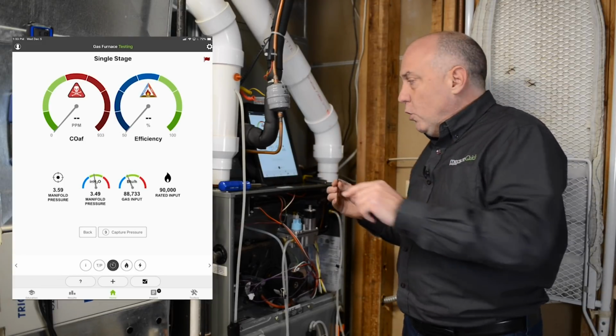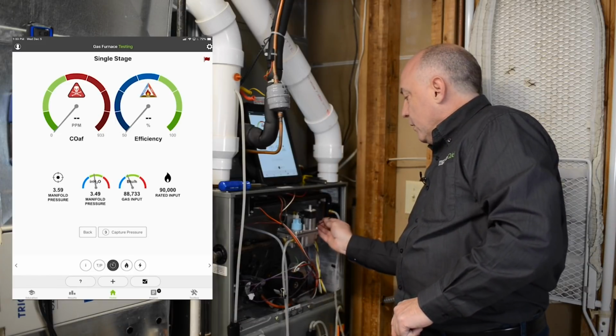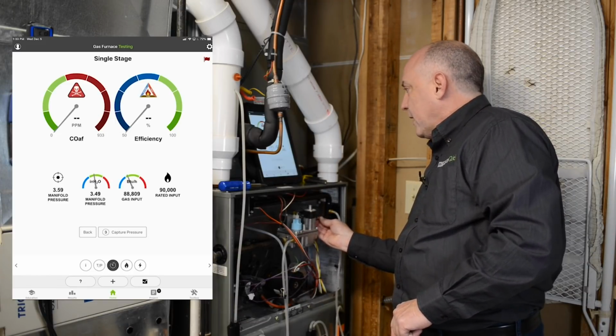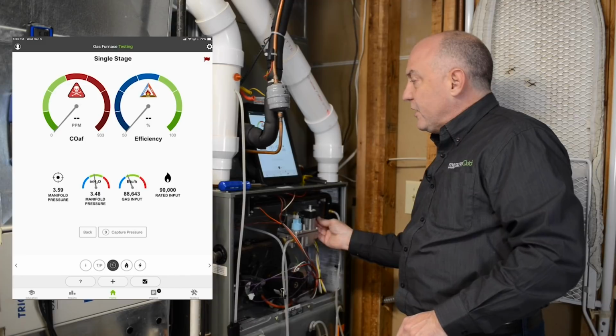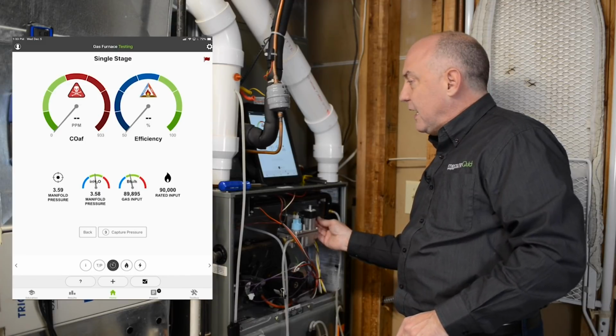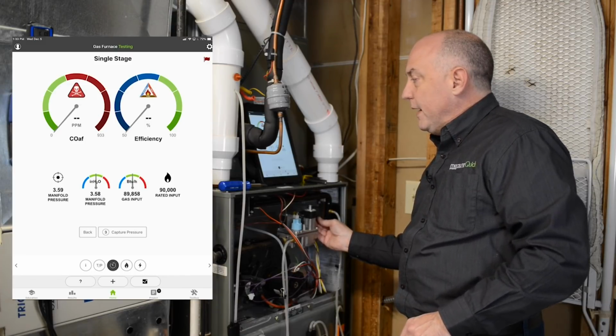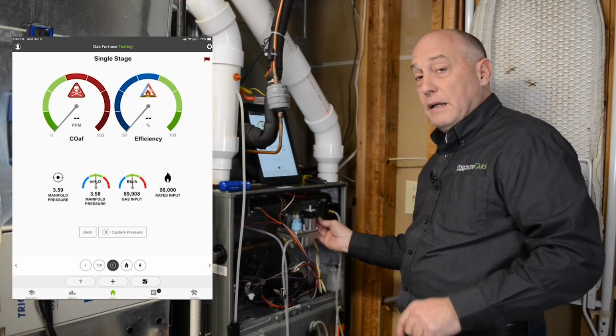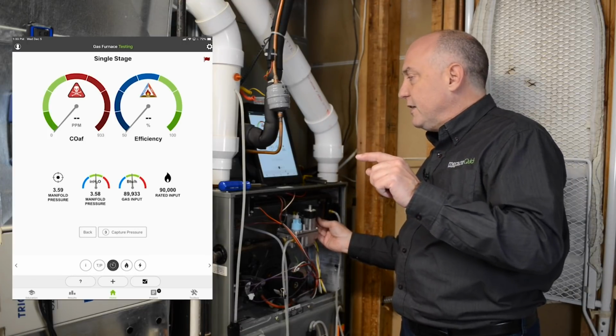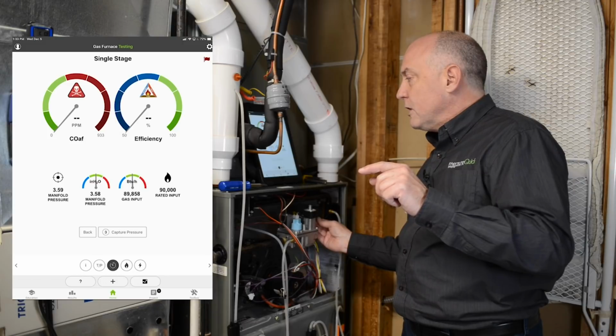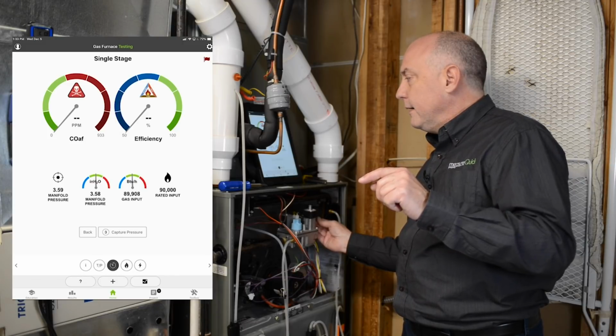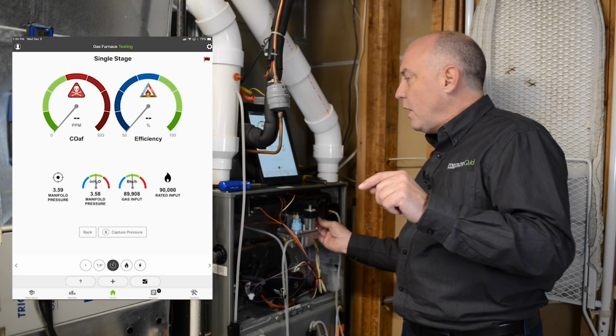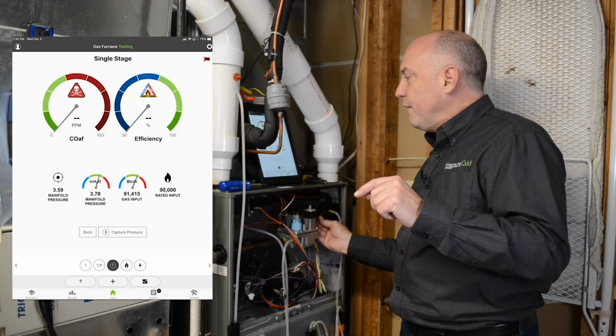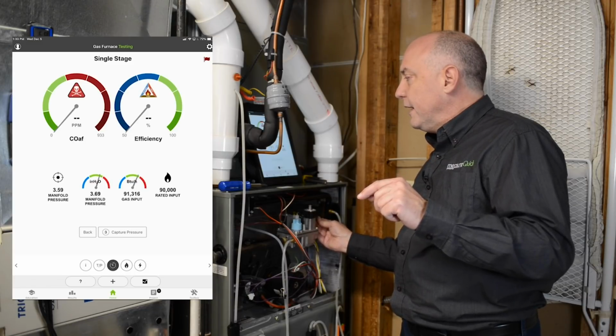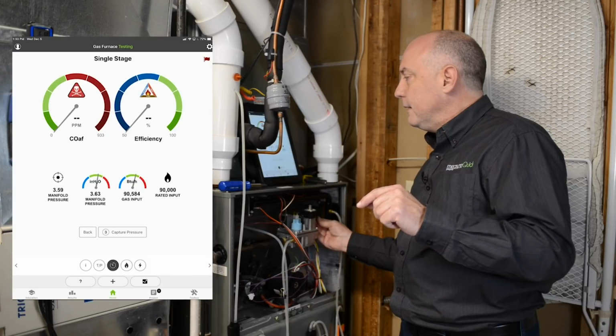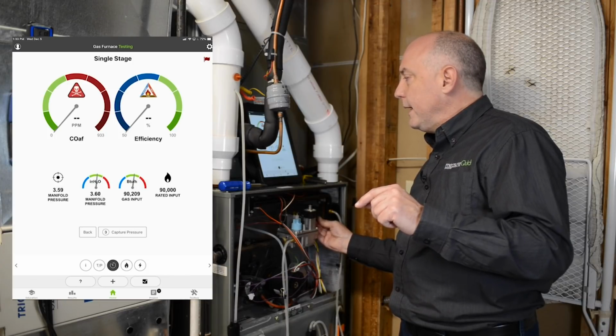Now this is where it's really cool. The manifold pressure we need is 3.59 inches of water column. So I'm going to dial this up, and you'll notice that as I'm dialing this up, you're seeing the BTU input increase at exactly the same time as my manifold pressure is. So we're continually recalculating that. I'm going to tweak it up just a hair more, get it right at 3.59 inches of water column. So I'm right at 3.59, a little overshot it just a hair there. We'll back it down a little bit, and we'll get that exactly where we want it.